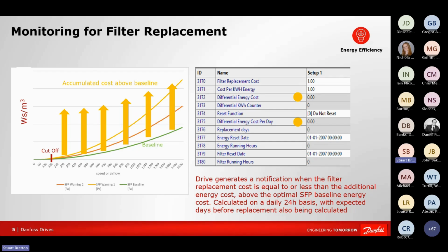So in an FC102, there are parameters that let you define, well, how much would it actually cost me to replace a filter? What is the kilowatt hour energy cost? And the drive can calculate every day how many more days it's going to take before it becomes more cost effective to replace the filter than to keep running the drive. So that's just one very simple example of how we can do condition-based monitoring in a standard drive.